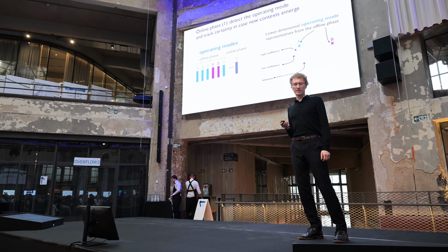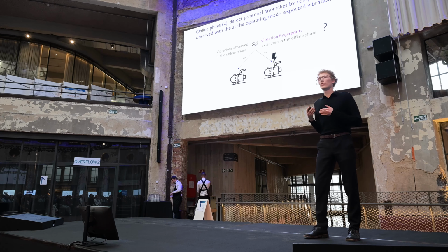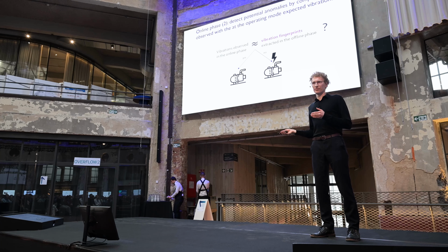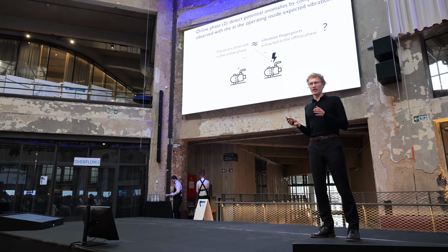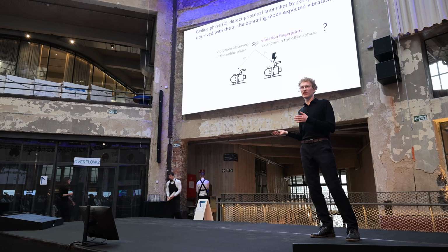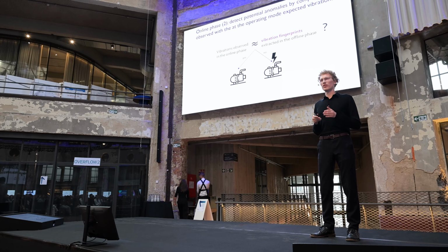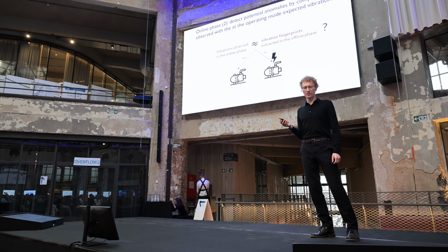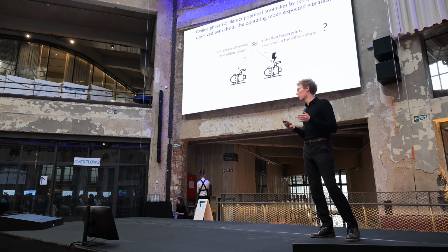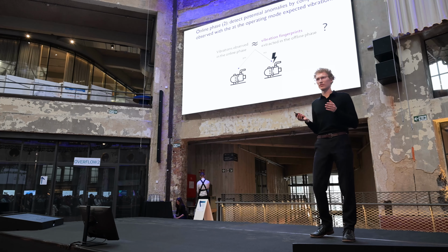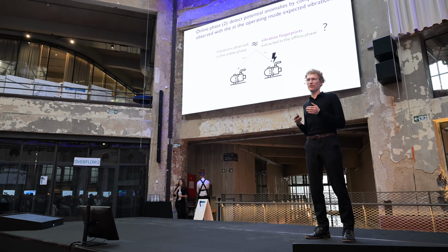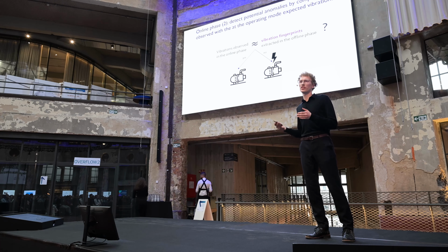Once the operating mode is detected, we can turn to the actual contextual anomaly detection. This is done by looking at the vibration fingerprint and comparing the observed vibrations of the given context to the contextual fingerprint. If it's approximately the same, then there shouldn't be any problem. But if there's a bigger difference between the two, then this is a sign for potential fault, and the equipment should be checked up.